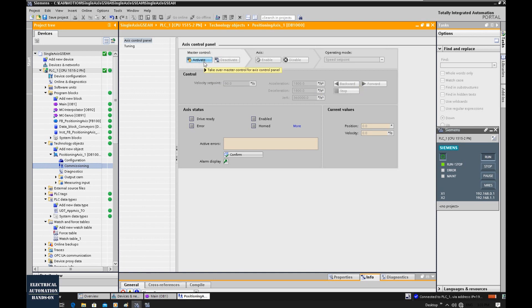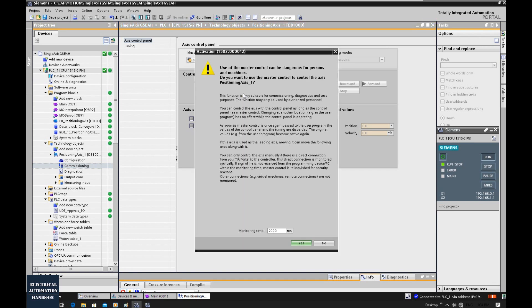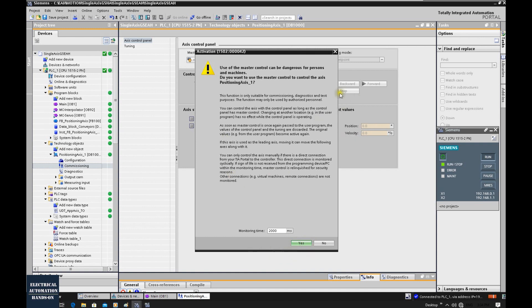We can click activate. It will mention this because once we hit forward or backward, it will actually drive the load. Keep in mind this very carefully. If your system has an e-stop or safety control, you should hold that e-stop in case your system does something wrong.